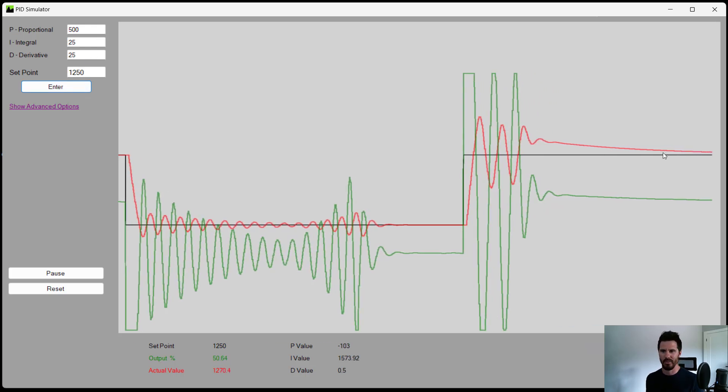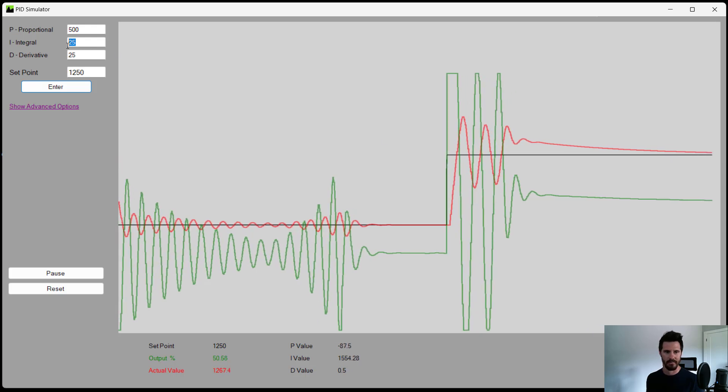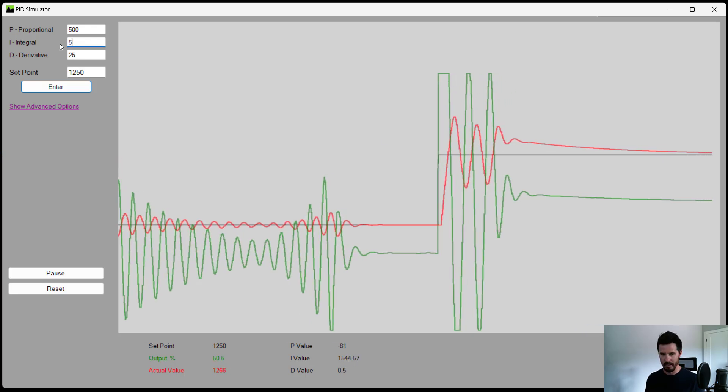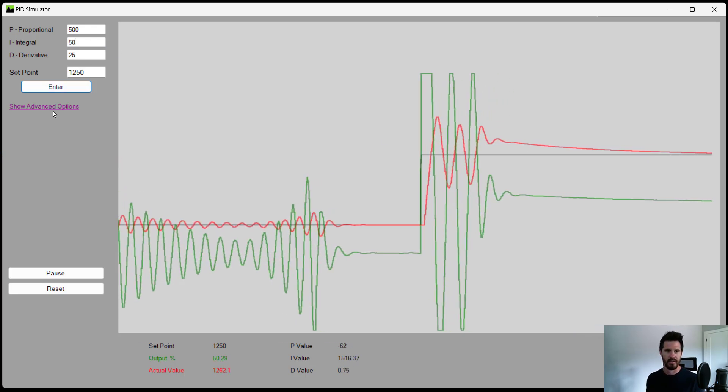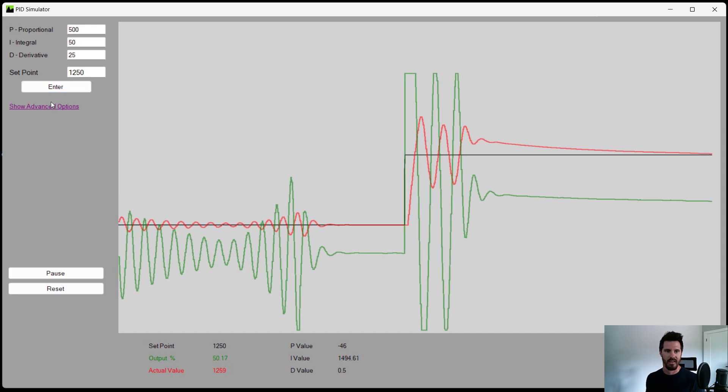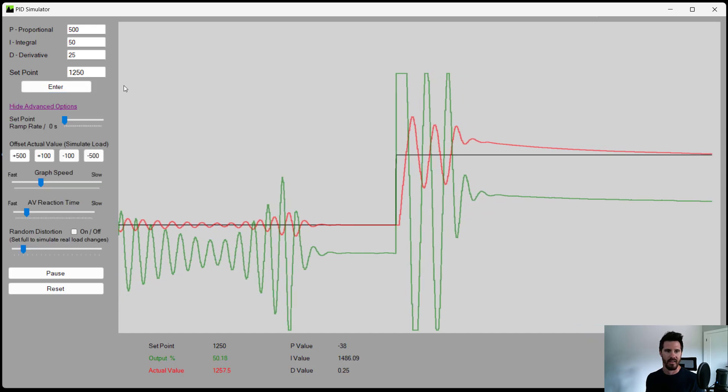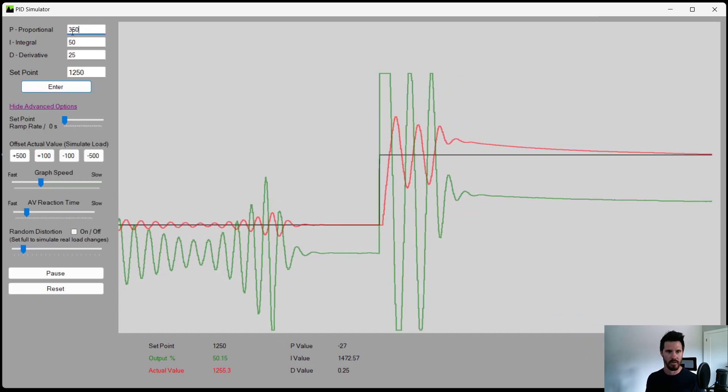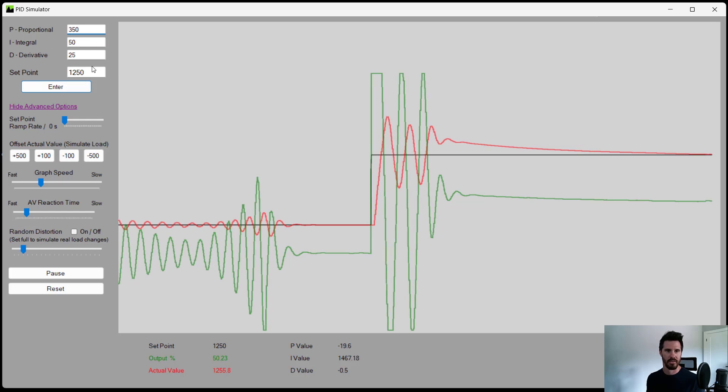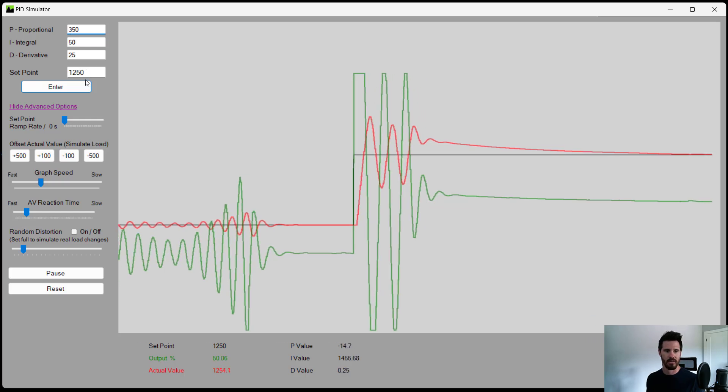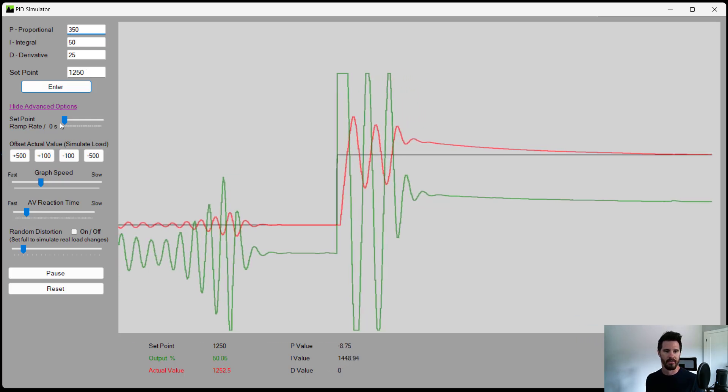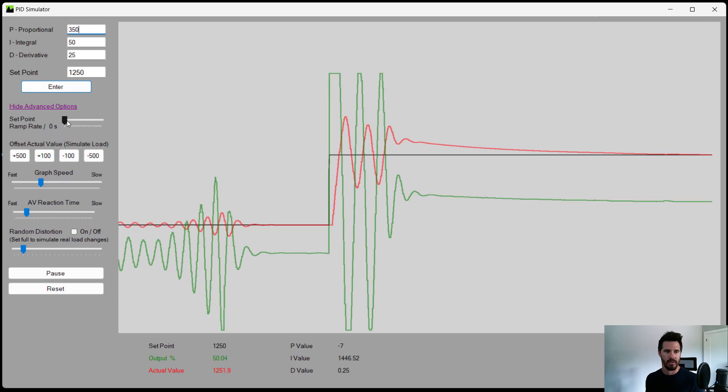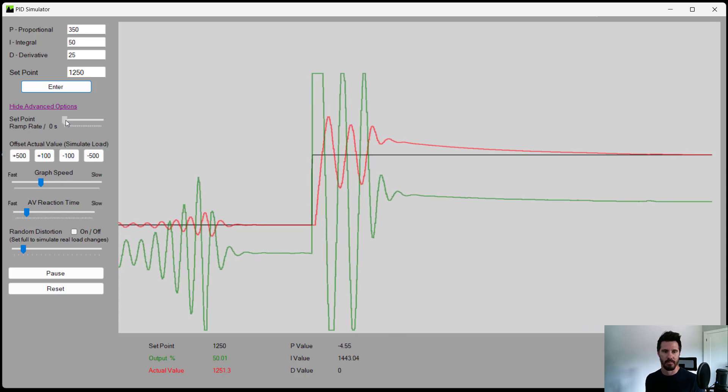All right. Integral is a little bit low, so it takes just too long to reach the set point. So back up to our starting place at 50. Now, I remember original proportional was 350, and that seemed to be pretty stable. Now, with the simulator software, you can change things like the set point ramp rate.